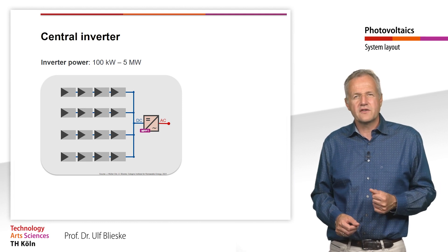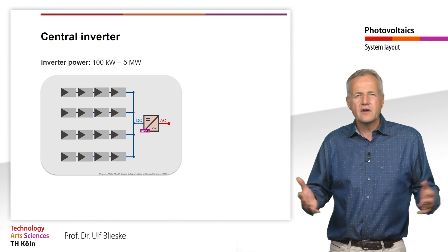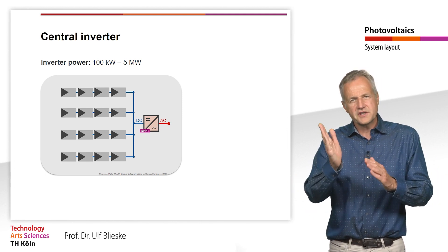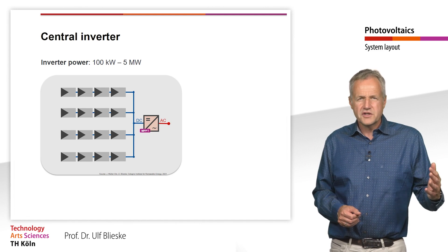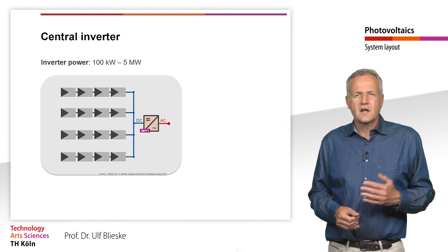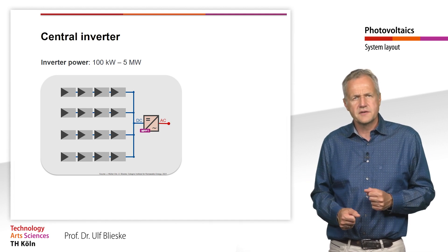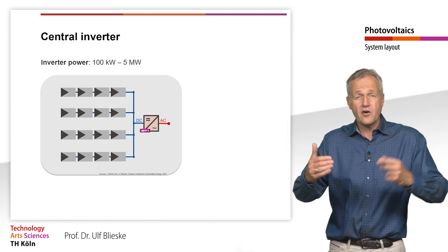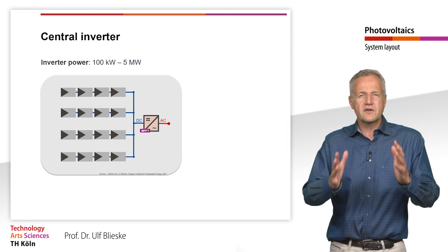This naturally leads to mismatch losses, which are higher compared to a system with many multi-string inverters. However, a system of this size is usually a ground-mounted system on which all modules have the same orientation. The mismatch between modules here is mainly due to the electrical parameters, voltage drops in the line and the partial shading or soiling of the modules. The relative losses due to mismatching are usually in the range of 1-3% for a central inverter. In addition, the probability of inverter failure increases with each electronic component. As a result, a plant with many inverters has a higher overall risk of failure than a plant with a single inverter.